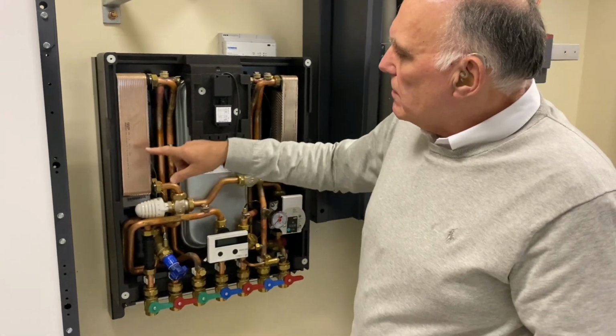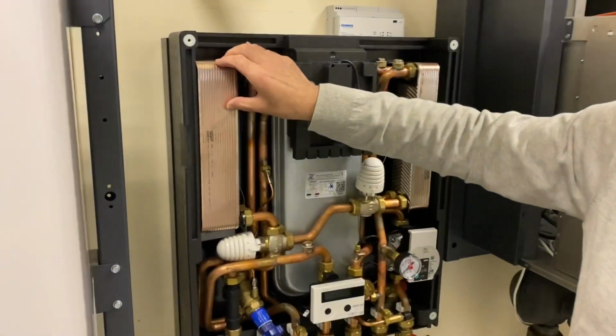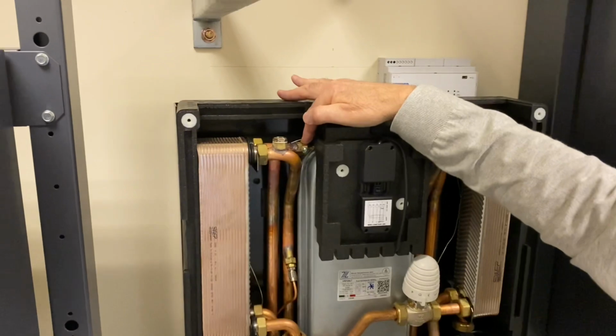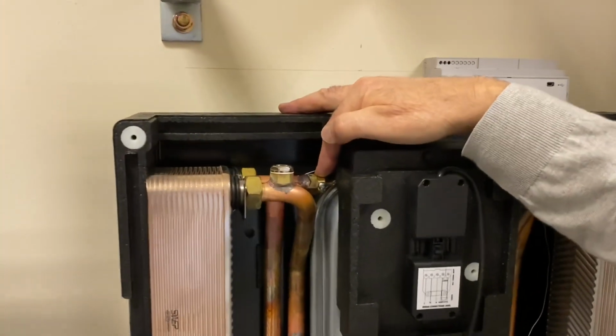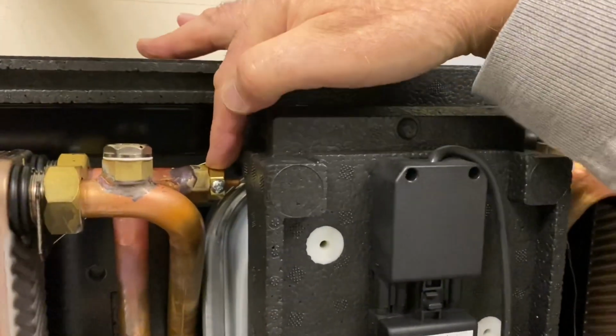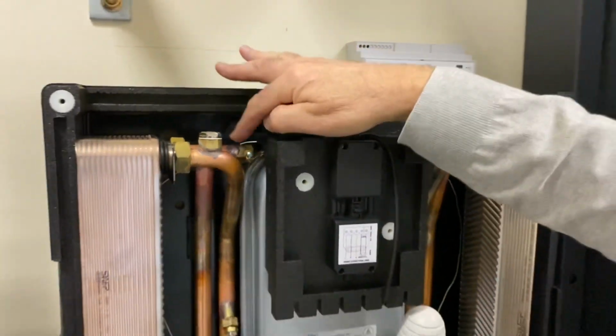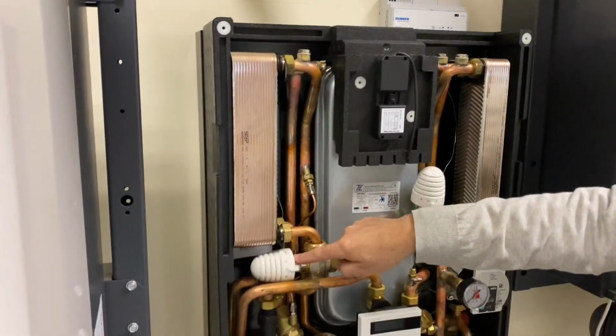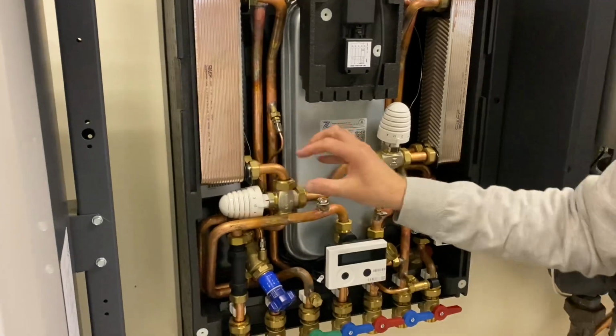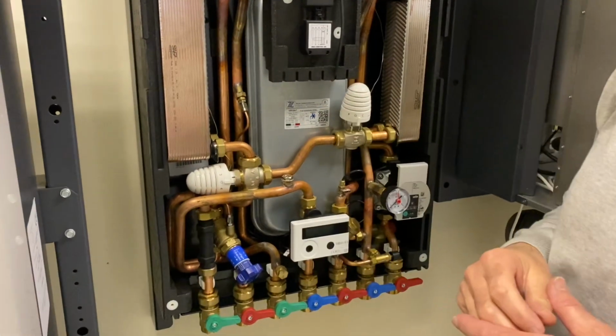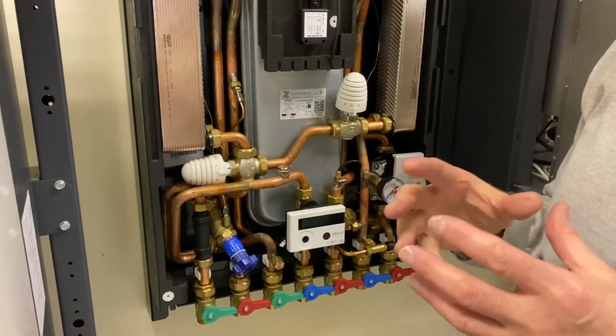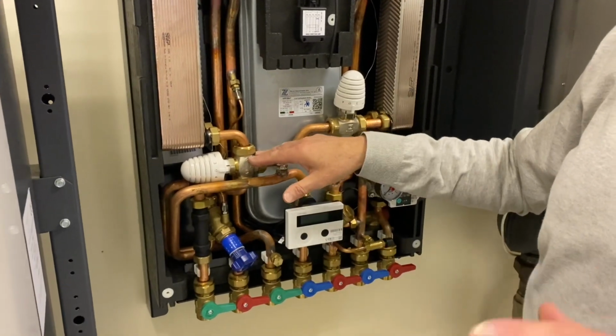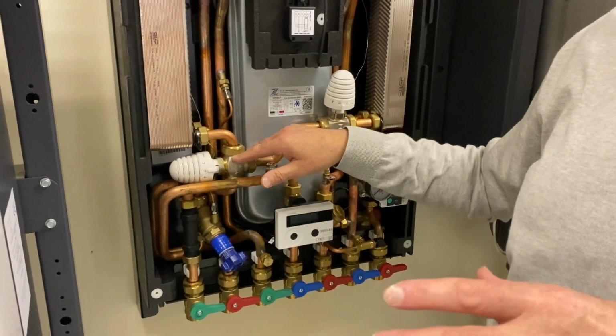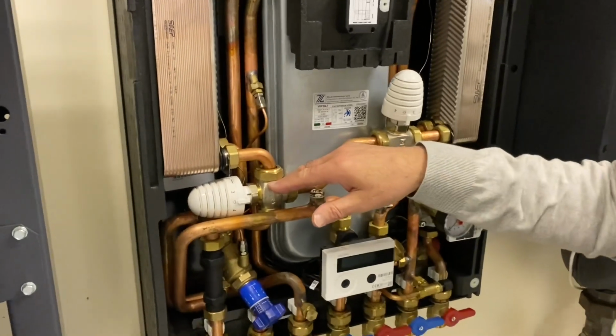So the primary flow comes in, heats up the domestic hot water. There's a sensor on the domestic hot water outlet from the plate heat exchanger, just under my finger, and that sensor acts upon this valve here. This is where the temperature of your domestic hot water is selected. The thing to bear in mind, I'll come back to this later, this is a proportional valve. It's not simply an on-off valve.